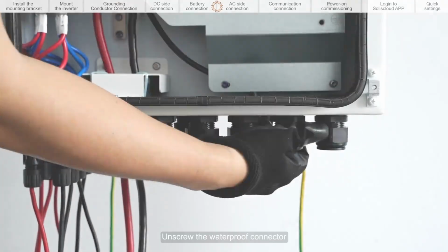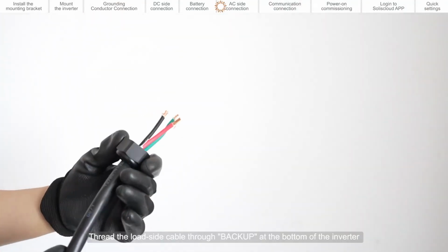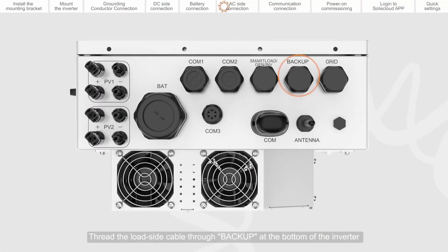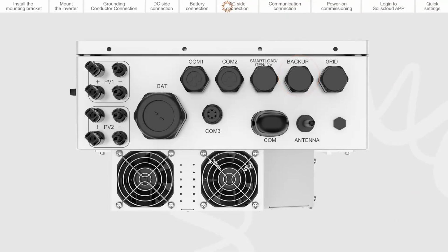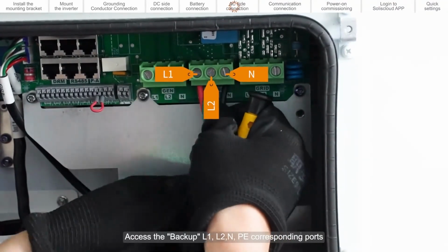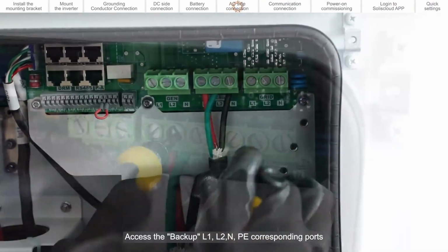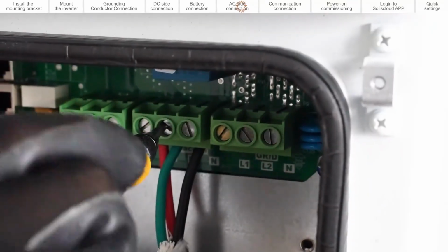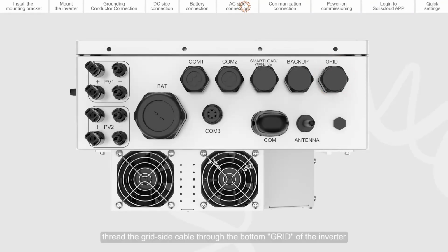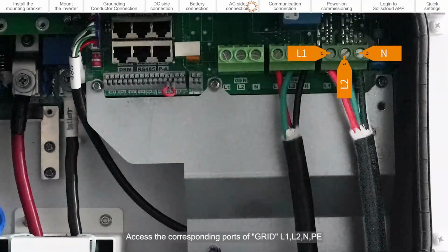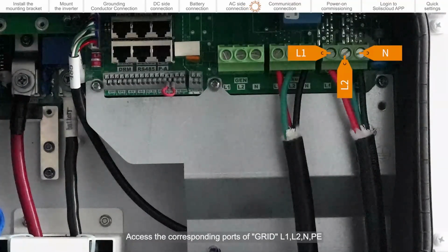AC side connection. Unscrew the waterproof connector. Thread the load side cable through backup at the bottom of the inverter. Access the backup L1, L2, PE corresponding ports. Similarly, thread the grid side cable through the bottom grid of the inverter. Access the corresponding ports of grid L1, L2, PE.